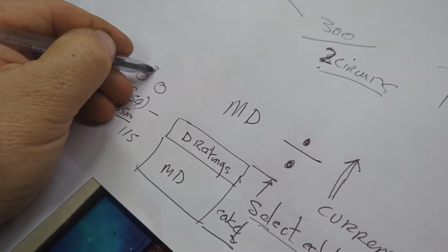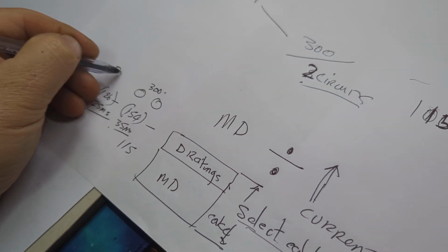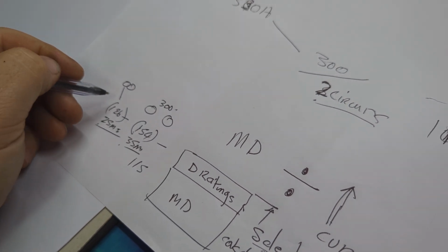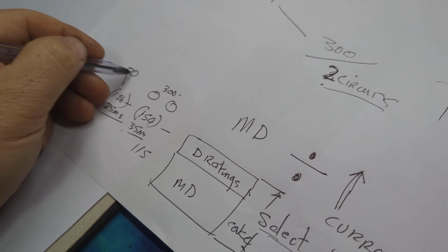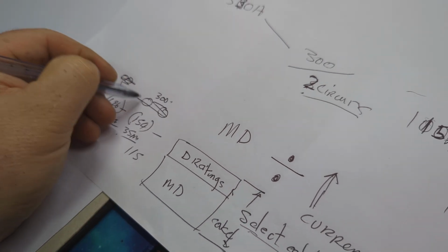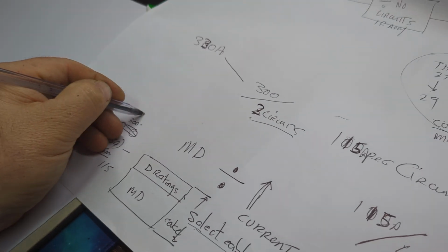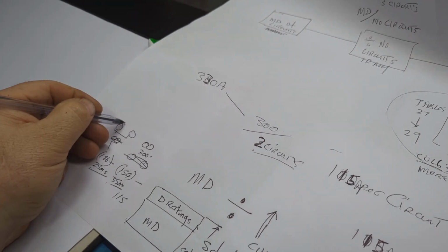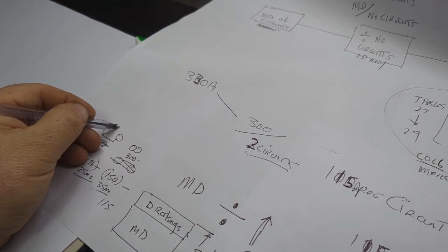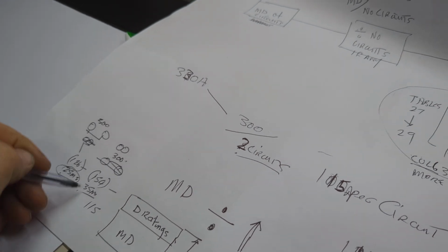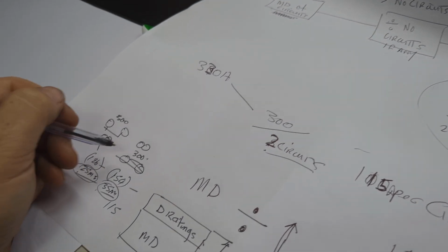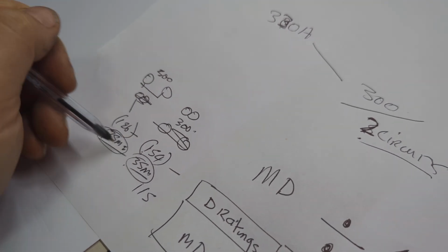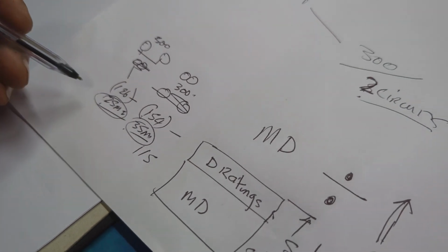This is 300 mil apart and this one was touching, and that's the difference. All right. Actually, sorry, the other way around. That one was touching. This one was 300 mil apart because we got less current and we got more heat dissipation. So 300 mil apart, 25 mil squared. Touching, we had to put a bigger cable in. All right. So that could be the difference in you losing a quote by size of cable.